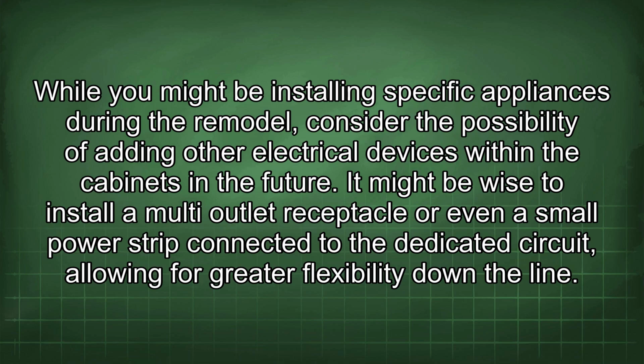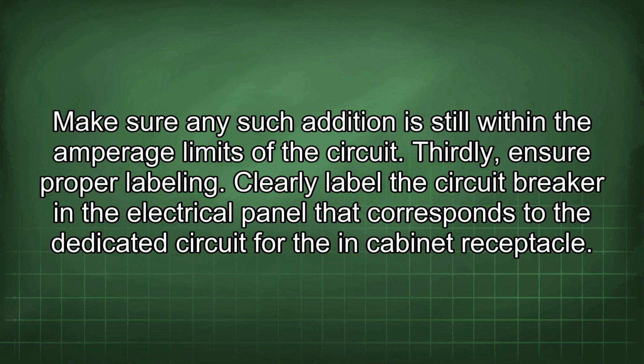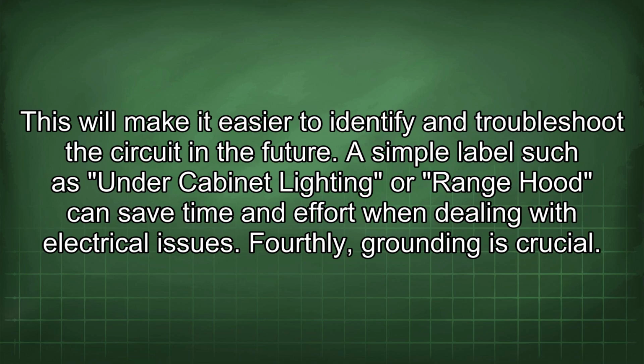Secondly, think about future needs. While you might be installing specific appliances during the remodel, consider the possibility of adding other electrical devices within the cabinets in the future. It might be wise to install a multi-outlet receptacle or even a small power strip connected to the dedicated circuit, allowing for greater flexibility down the line. Make sure any such addition is still within the amperage limits of the circuit. Thirdly, ensure proper labeling. Clearly label the circuit breaker in the electrical panel that corresponds to the dedicated circuit for the in-cabinet receptacle. This will make it easier to identify and troubleshoot the circuit in the future. A simple label such as under-cabinet lighting or range hood can save time and effort when dealing with electrical issues.